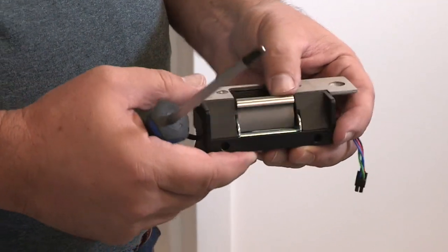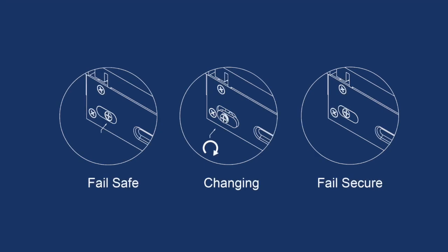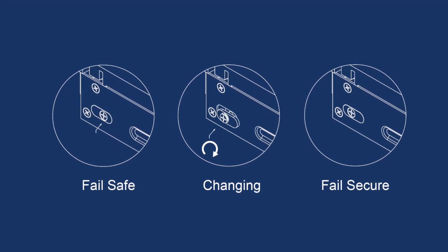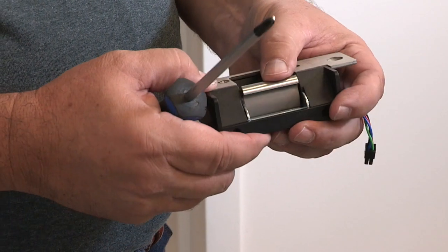Fail-safe means that the setting will unlock the strike upon losing power, and a fail-secure setting will lock the strike upon losing power. This strike is fail-secure.